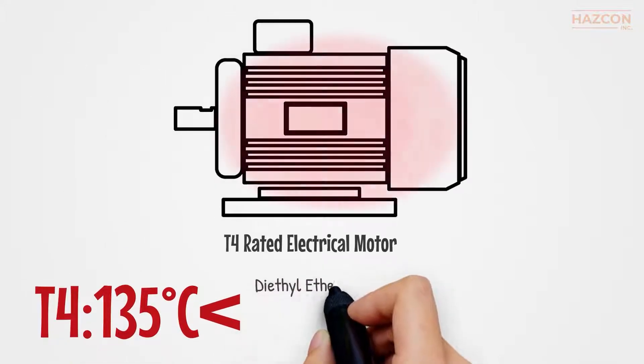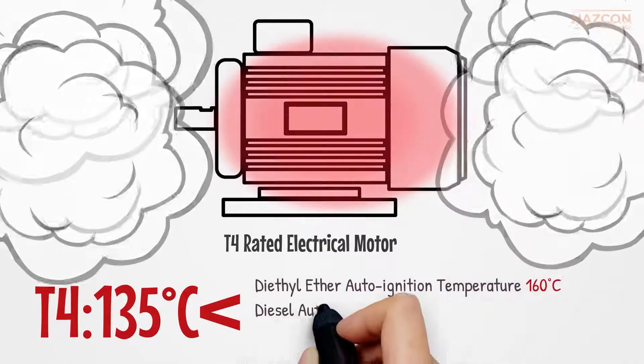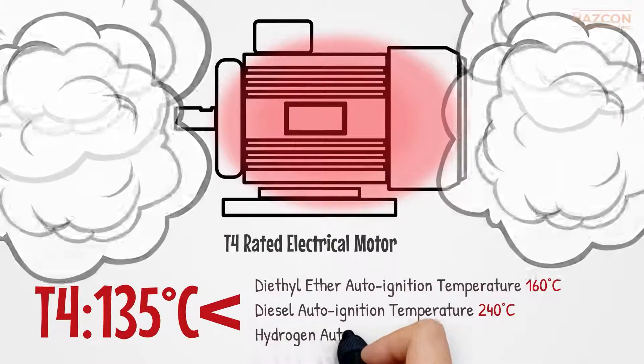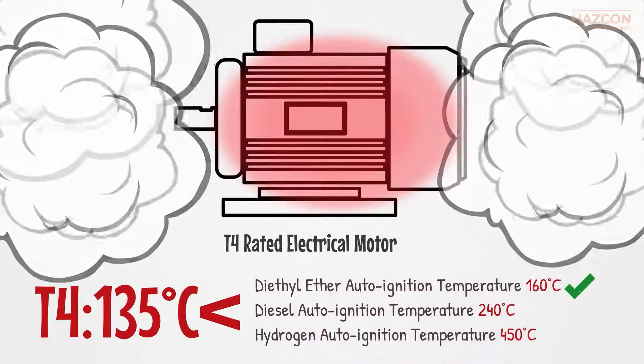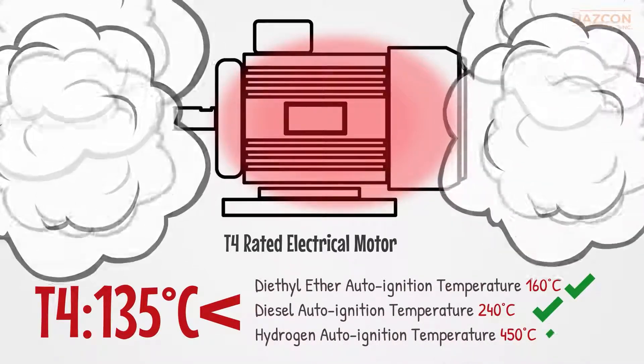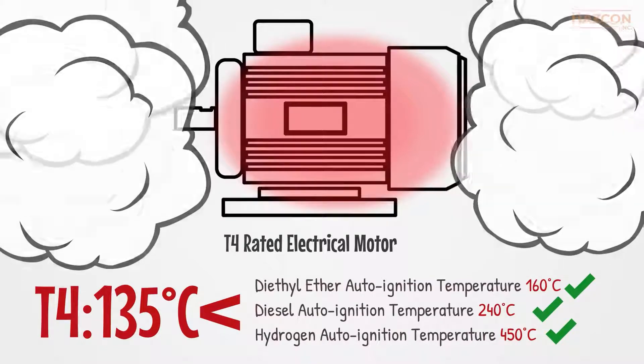Now this T4 rated electrical motor can be safely installed in an area when diethyl ether, diesel, or hydrogen are present because the minimum ignition temperature of these gases is higher than maximum surface temperature rise of our T4 motor.